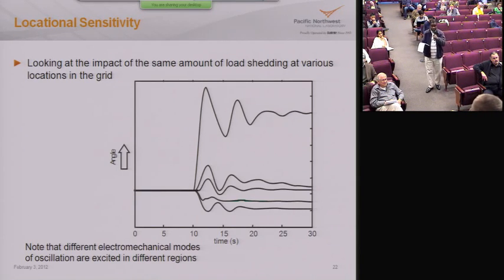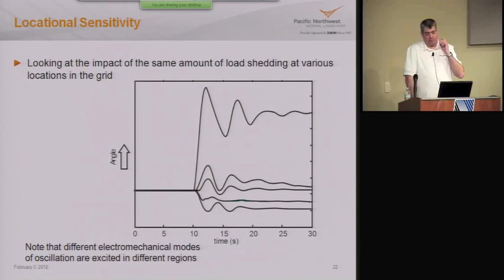That's right. What we did on this plot is fairly simple—every trace is the same angle pair in the system, and we're showing that between that same angle pair, we dropped load at different parts of the system. If you take a different angle pair and look at the angle difference, this plot will look different, but what stays the same is that you'll get more sensitivity for this particular location versus the rest. The shape of the curves might differ and the units will differ, but the answer is the same: this is the most sensitive place to shed load.